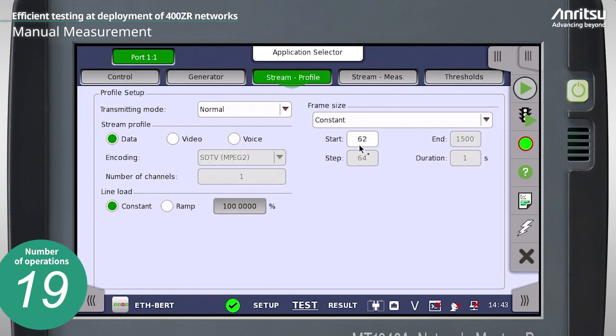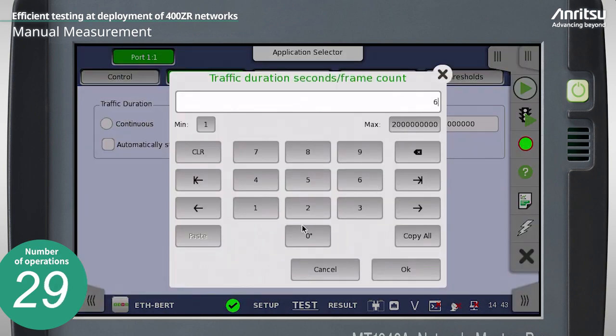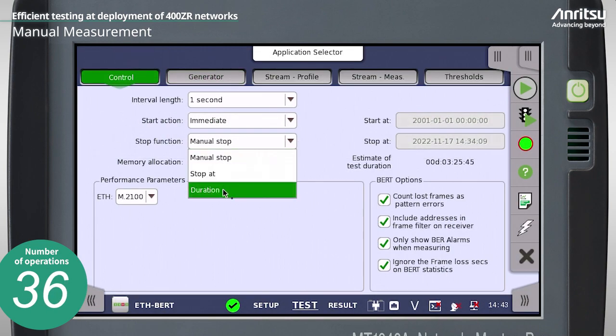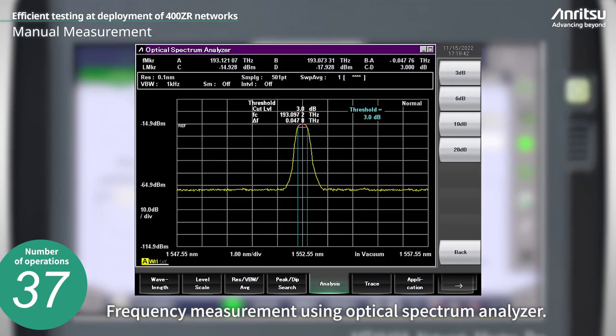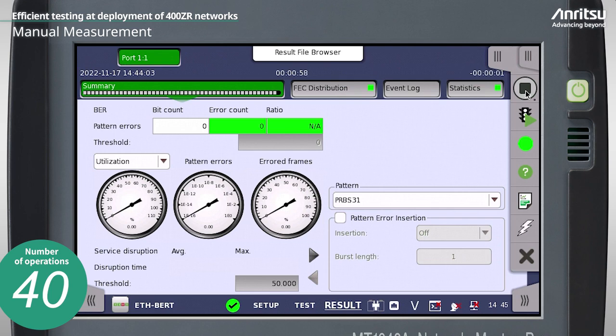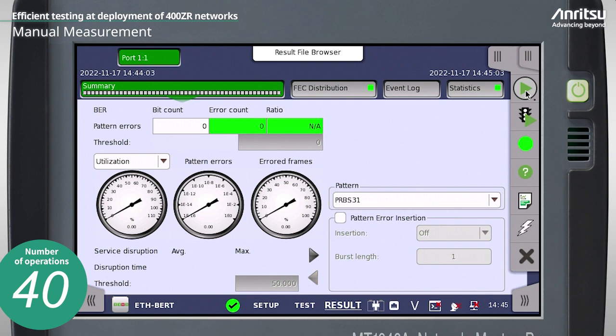As a result, the work documentation must be referenced step by step to make settings in the correct sequence and switch the fiber connection between the 400G test module and the OSA at the correct timing. After measurement, the operator selects test results visually and then checks the on-screen pass-fail evaluation.